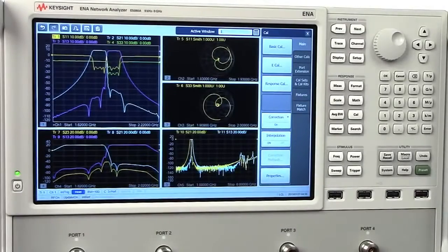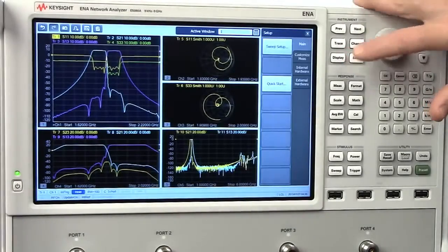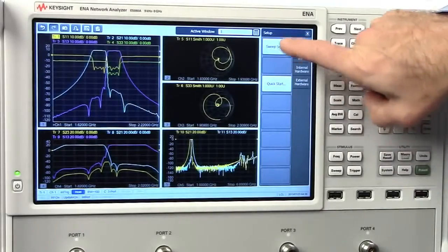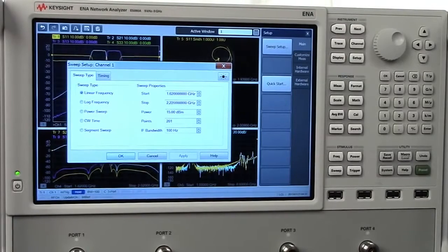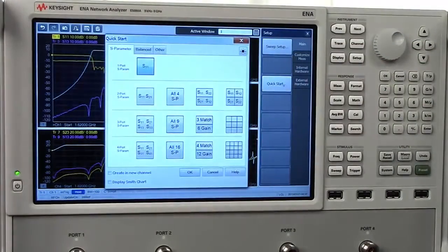In many cases, the best way to quickly start a measurement is the Setup key in the instrument group. Pressing Setup activates a soft key menu that has two choices: Sweep Setup and Quick Start. Choosing Sweep Setup opens a window containing a single dialog menu that presents the fundamental measurement parameters. Quick Start goes a step further by providing access to dialog menus that let you open a variety of templates for common measurements.